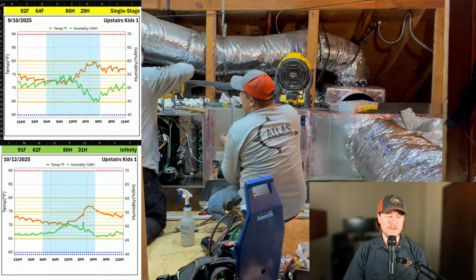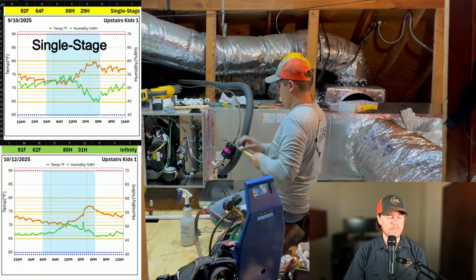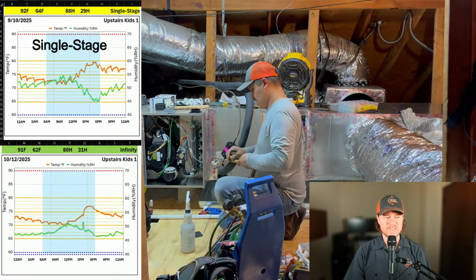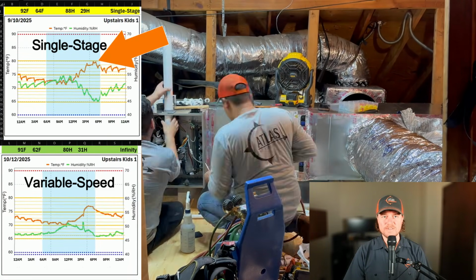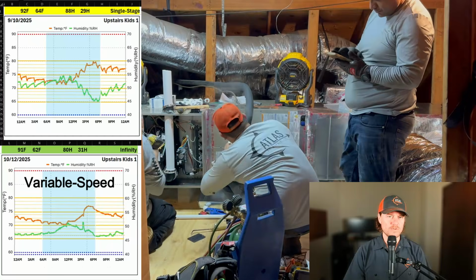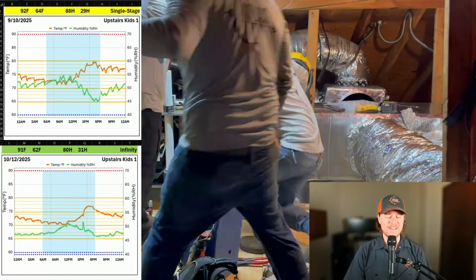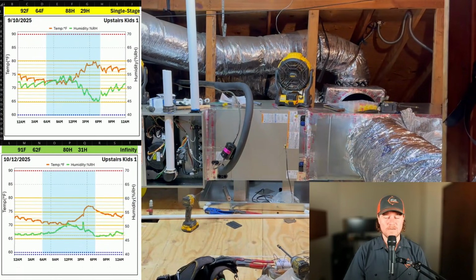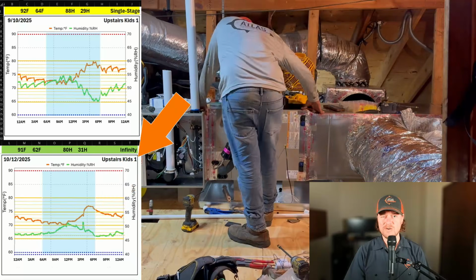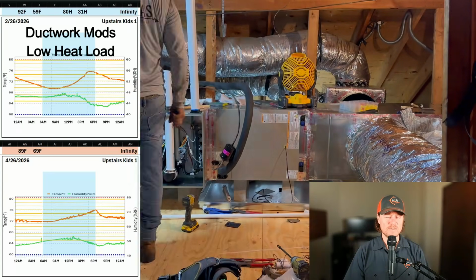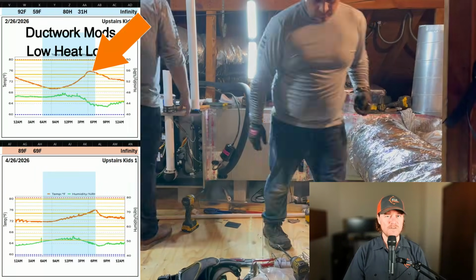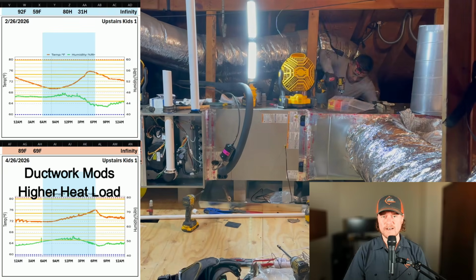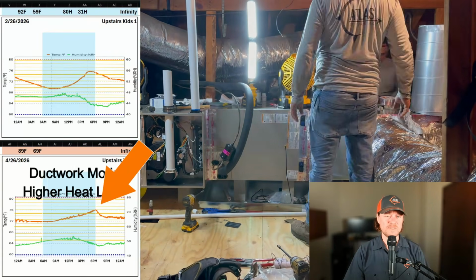In my daughter's room, as you can see here, the orange line that is representing the temperature in that room, you can see it touching on 80 degrees. We then replaced the HVAC system with a fully variable speed system without modifying any of the ductwork, just to see how much it can improve. And it did make some pretty good improvements, but it only got us about halfway there. Here's after we made the ductwork modifications, and it was made clear to me that we probably did not fix the problem. And sure enough, that was indeed the case.